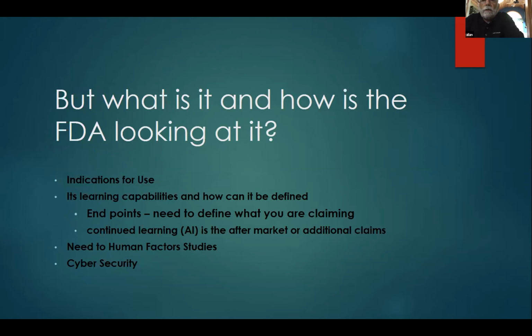What is the FDA looking at, and how is the FDA looking at it? Anytime you have a submission, the first thing that the FDA is looking for in your device is, again, the indications for use of the device. What we find is that many people are going very, very broad on their indications for use. This is a mistake. It's better to almost do a creep. Get your device through the FDA with a narrow focus on your indications for use. Once you have that through the FDA, you could always go back to the FDA and broaden your claims. We find that's the best way for dealing with FDA.